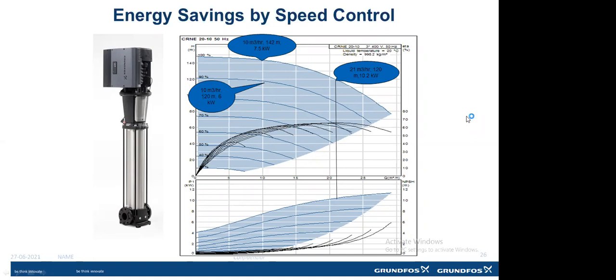Yeah. So it depends on the flow requirement over the period of time. If our flow requirement keeps changing drastically, let's say, for example, in the morning my requirement is 20 meters per hour, and in the evening my requirement is 70 or 80 meters per hour. We cannot operate the same pump for 20 meters as well as 80 meters per hour, right? So in that case, what we can do is install 3 pumps of capacity 30 meters per hour each. And if our requirement is varying from only 50 to 80 meters per hour, we can use only one pump, because the pump will be operating from 50% to 100% of the capacity. So it depends on how your demand is varying over the period of time.